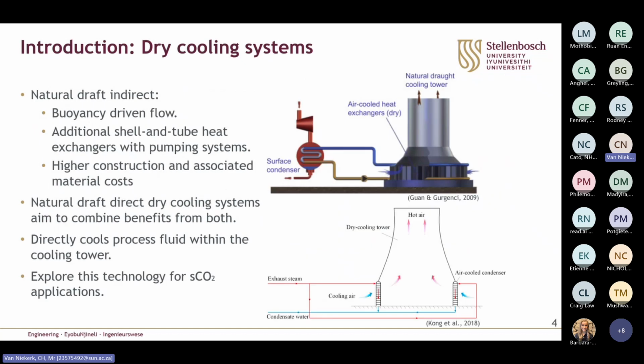Natural draft indirect dry cooling systems use buoyancy-driven flow to drive air across the air-cooled heat exchangers situated in the base of the cooling tower. This mitigates the need for fan drivetrains and minimizes the operational power consumption of the plant. However, these cooling systems require additional shell and tube condensing heat exchangers connected to pumping networks to cool down the turbine exhaust steam, which increases the system complexity.